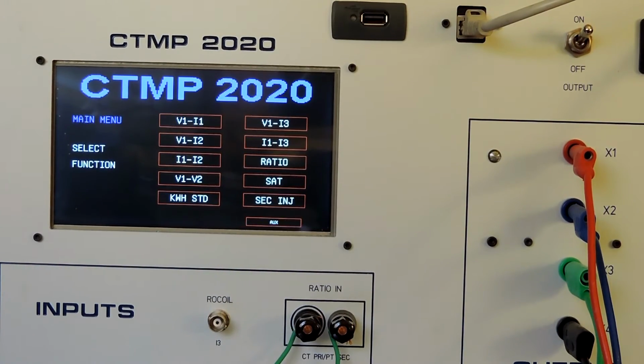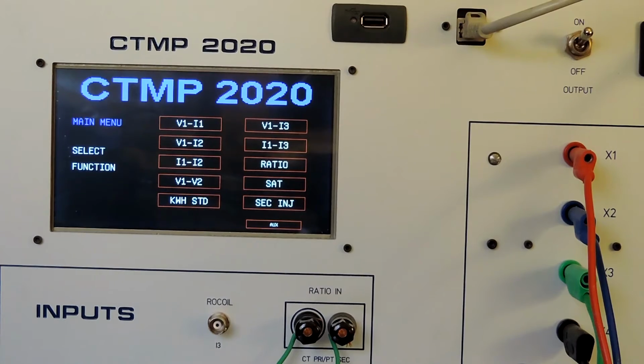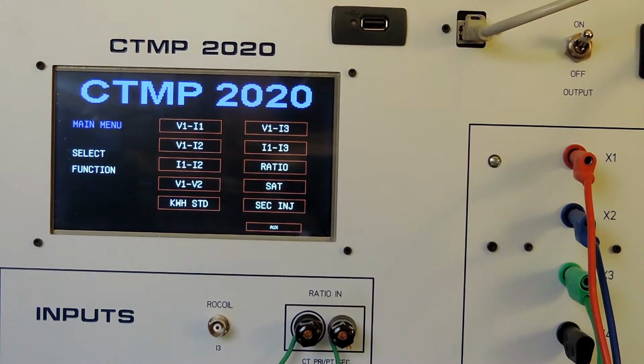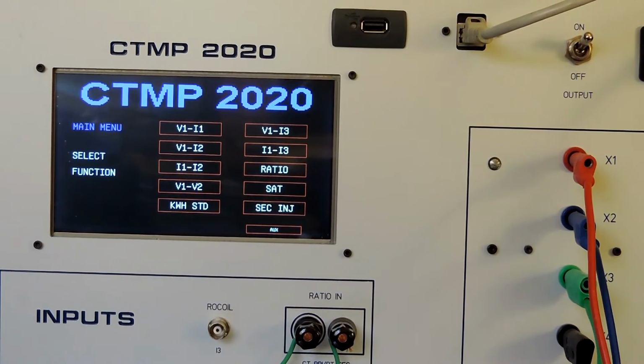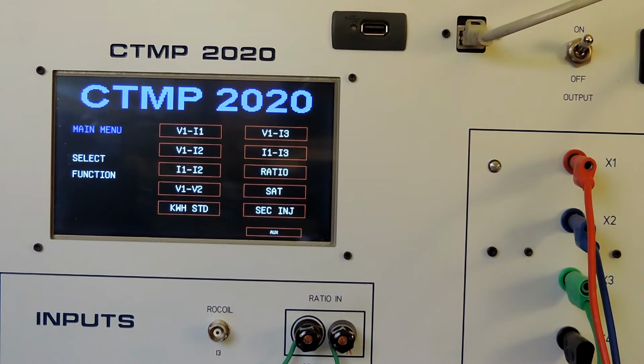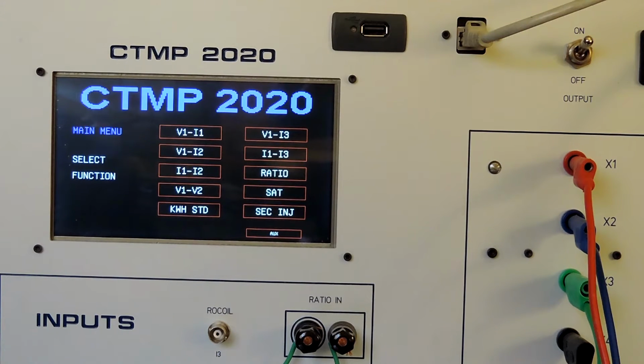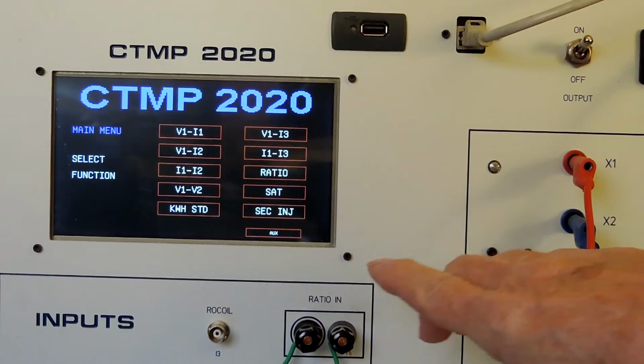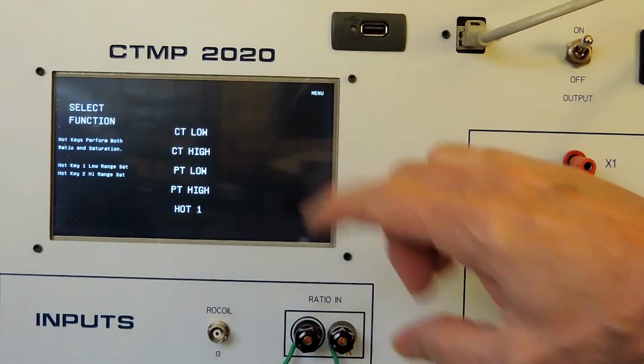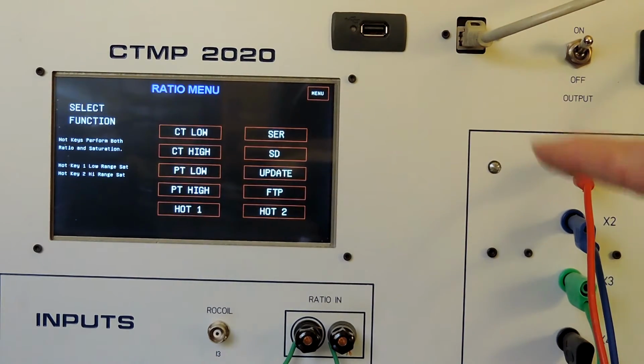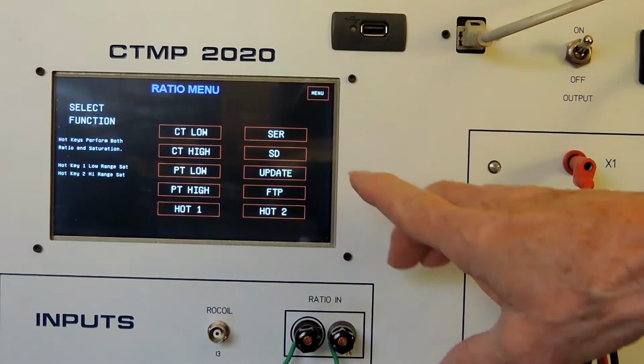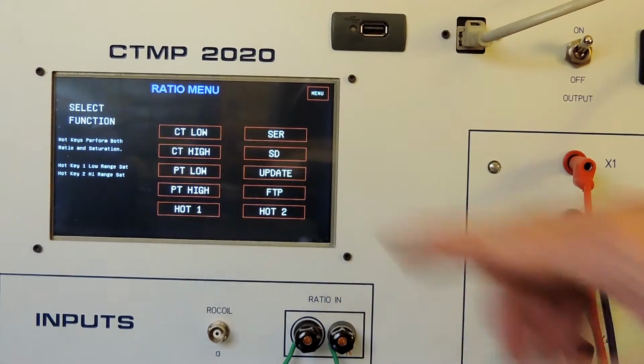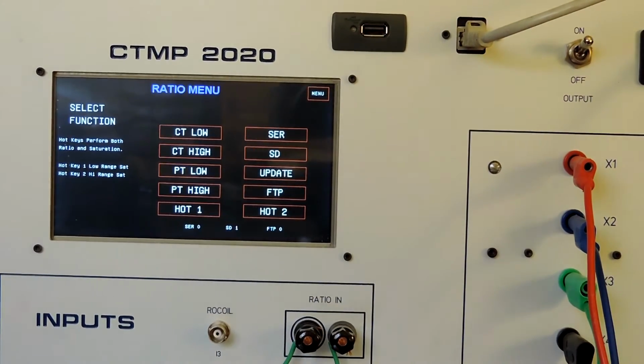Okay, this is a little demonstration of what I call the smooth and easy CT testing provided by the CTMP 2020. I have it connected to a 2000:5 multi-tap CT. So all I have to do is press ratio. The hotkeys do both ratio and saturation. I want to save it to the SD card.